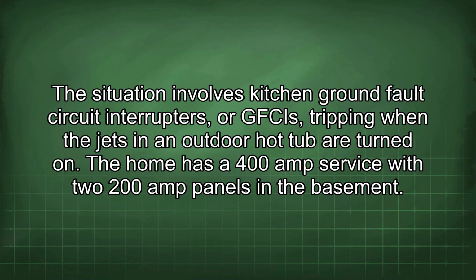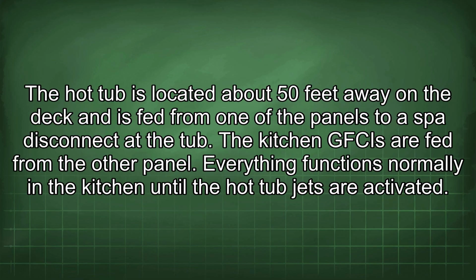The situation involves kitchen ground fault circuit interrupters, or GFCIs, tripping when the jets in an outdoor hot tub are turned on. The home has a 400 amp service with two 200 amp panels in the basement. The hot tub is located about 50 feet away in the deck and is fed from one of the panels to a spa disconnect at the tub.